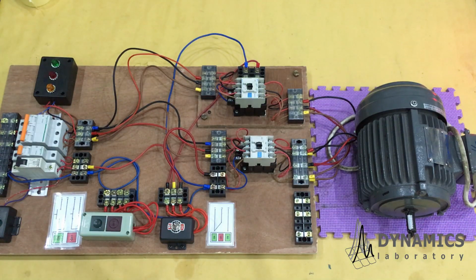Let's see the circuit. To reverse the rotational direction of three-phase AC motor, you have to change the connection between coils and voltage line. For example, clockwise rotational direction, we connect the U, V, and W coils with R, S, and T voltage line respectively. Then, for counterclockwise rotational direction, we should change two connections and one connection remains the same. The connection between U coil and R voltage line are still the same, but we connect V coil with T voltage line and W coil with S voltage line. That's what we do in here.